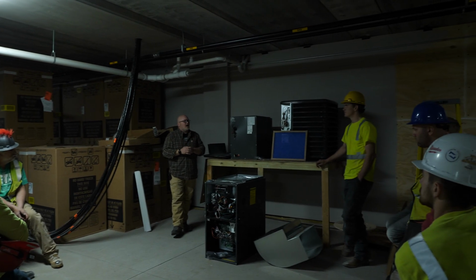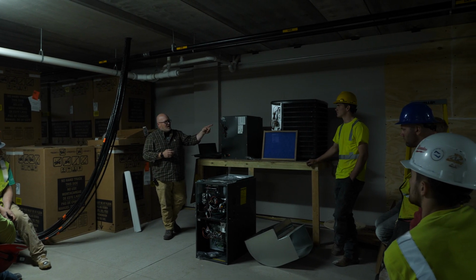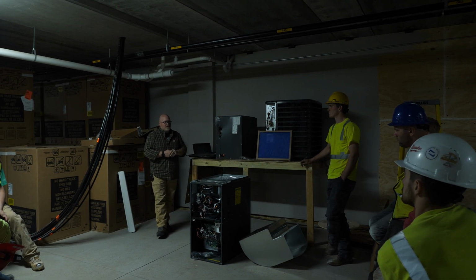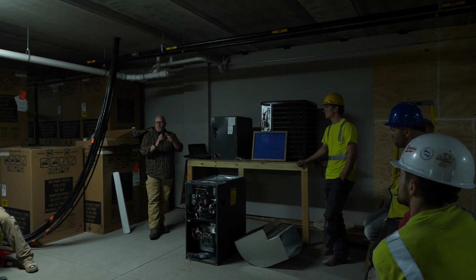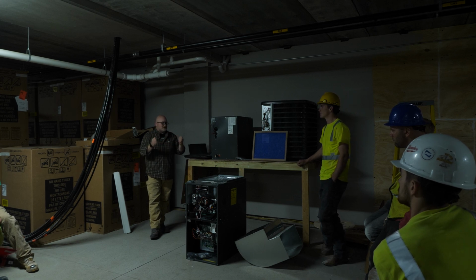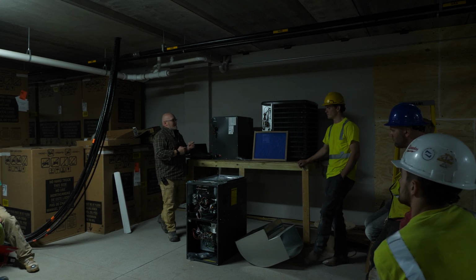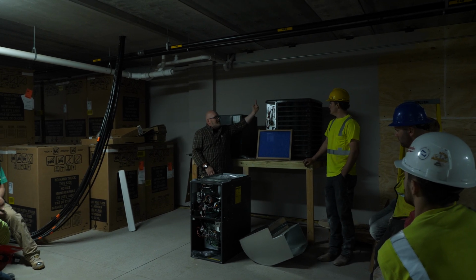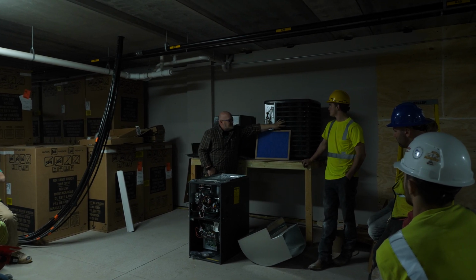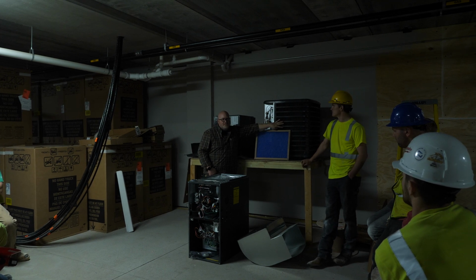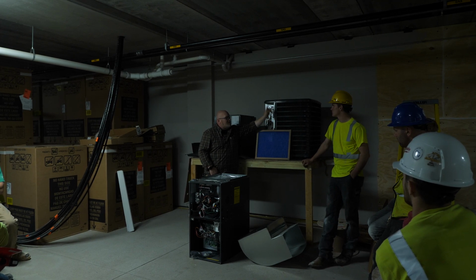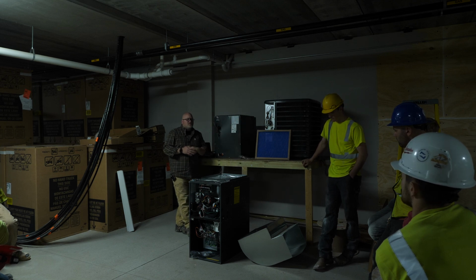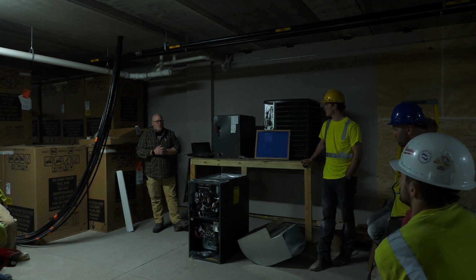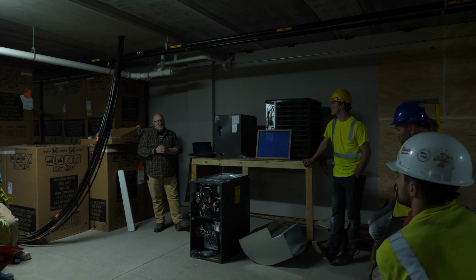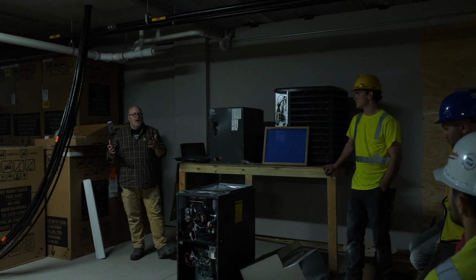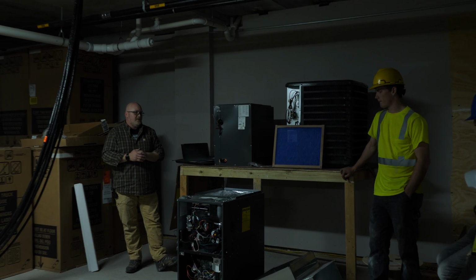If you took a thermal gun and put it on a condenser coil outside, you could actually see the hot spots where those fins were bent over, because they're just not able to reject heat. And remember that fan on top is blowing heat upwards. So it is literally sucking everything from the outside in through that coil and then up. And generally, most households, you're looking at once or twice a year having those coils cleaned. But again, it really depends on where you live, what type of environment you live in.